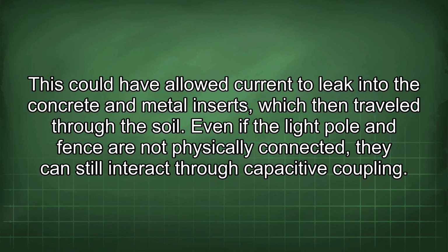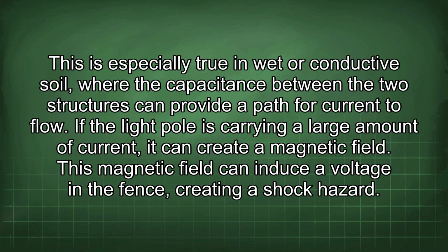Even if the light pole and fence are not physically connected, they can still interact through capacitive coupling. This is especially true in wet or conductive soil, where the capacitance between the two structures can provide a path for current to flow. If the light pole is carrying a large amount of current, it can create a magnetic field. This magnetic field can induce a voltage in the fence, creating a shock hazard.